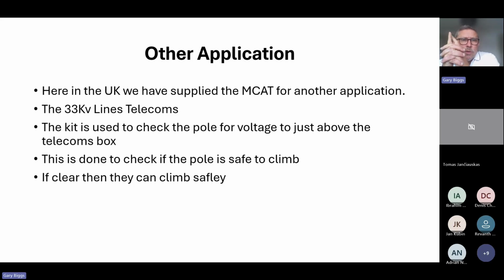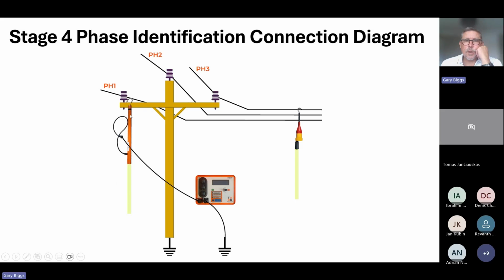So in the UK, we also have pole mounted 33 kV lines. And on those lines, they have telecom boxes about 2/3 of the way up the pole. Now, we have sold the unit where we would take the voltage probe and move it all the way up the pole to just above the telecom box. Obviously, if the pole shows no residual voltage, that means the linesmen know that that pole is safe to climb and work on the telecom box. If, of course, they find that the pole itself is showing a voltage, then they know that they need to access the telecom box not on a ladder or climbing, but via a bucket and lift, as it were.